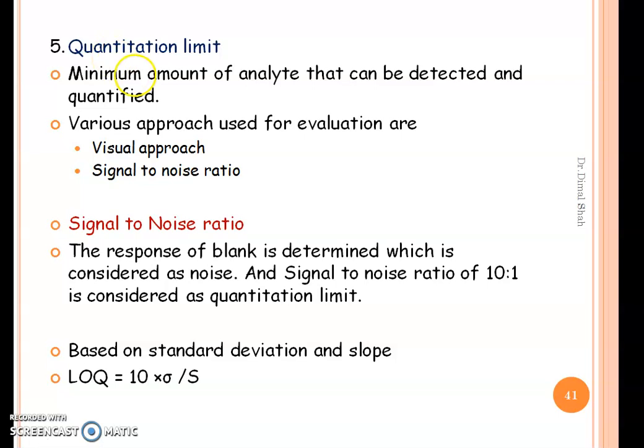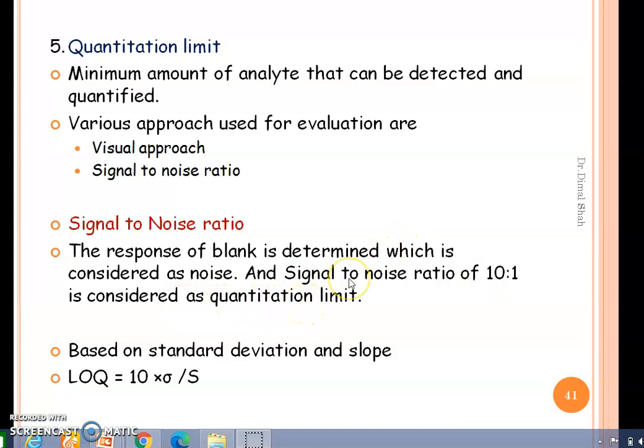The fifth parameter is quantitation limit, which indicates the minimum amount of analyte that can be detected and quantified. The various approaches used for the determination of quantitation limit are the visual approach and signal-to-noise ratio. In the signal-to-noise approach, the response of blank is determined and considered as noise, and a signal-to-noise ratio of 10:1 is considered as the quantitation limit.